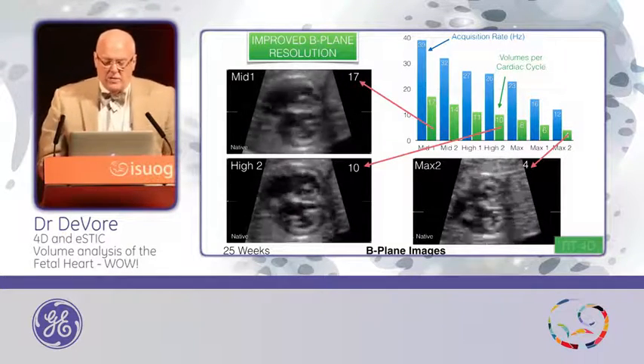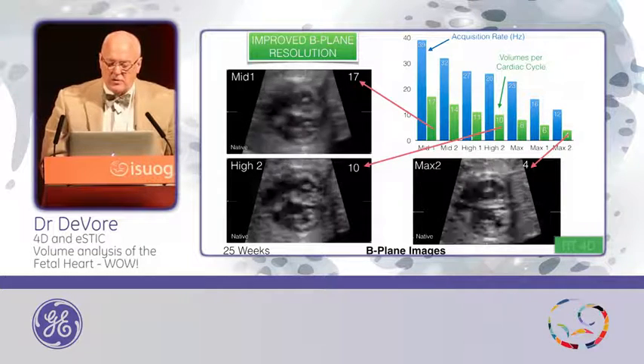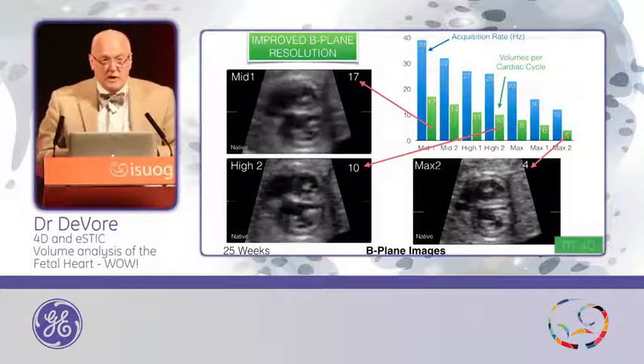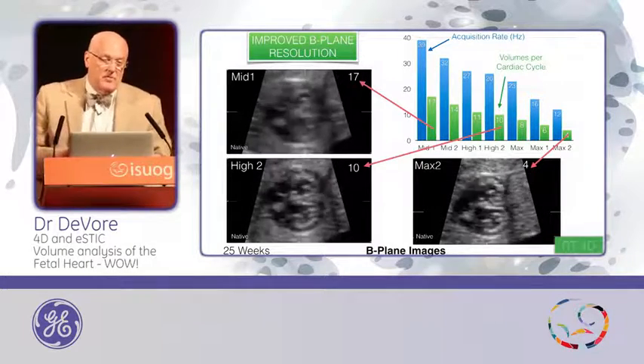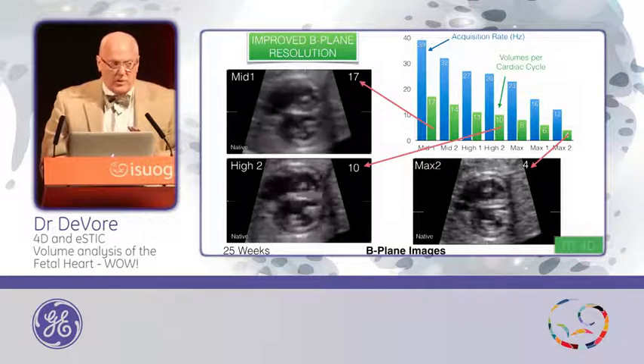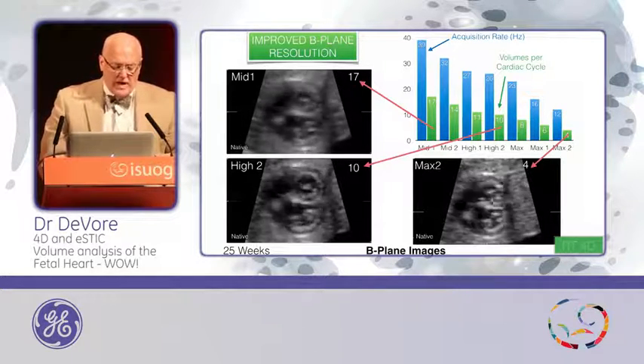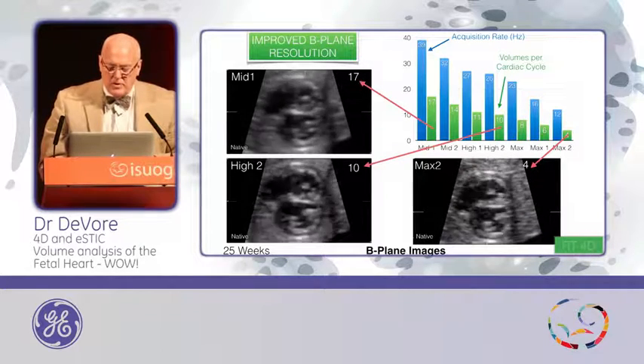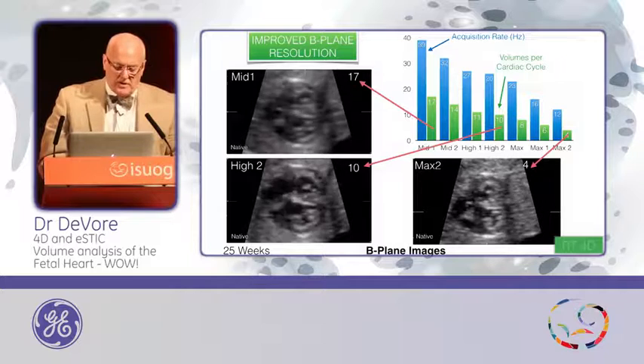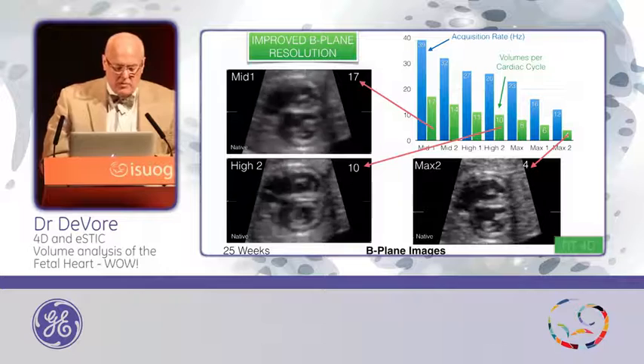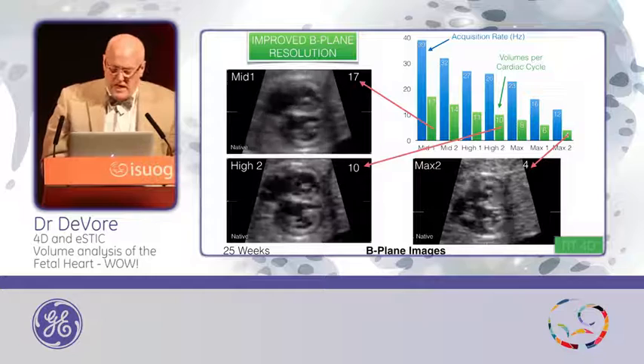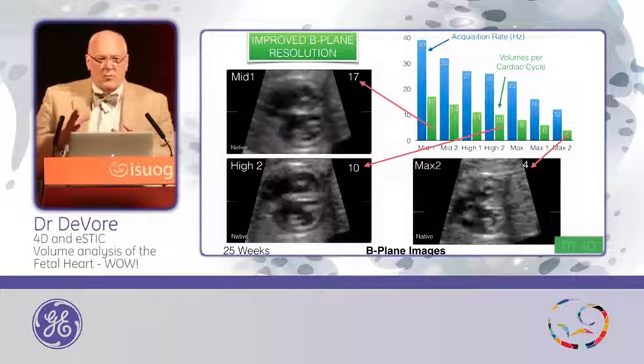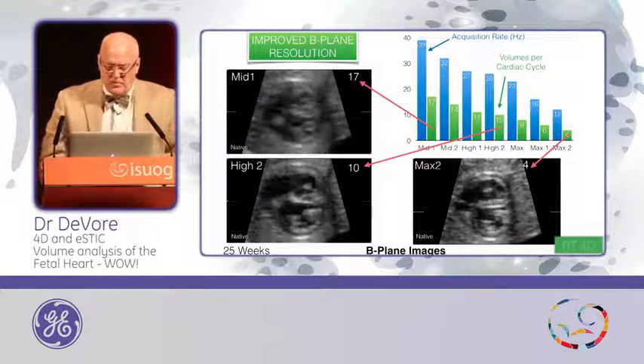It's important to realize that the acquisition rate on screen — you may see 39 Hz, 32 Hz, 27 Hz — the actual frame rate is approximately half of the Hz shown, because a cardiac cycle in the fetus usually lasts less than half a second. To illustrate the principle: these are B-plane images of the short axis of the heart showing the tricuspid valve, pulmonary valve, mitral valve, and ventricular walls. At mid-resolution of 17, you have a volume rate of 17. At higher resolution, image quality improves but volume rate drops to 10. At maximum resolution, the volume rate is 4. You play with those two variables by adjusting the length of the B-mode sweep.